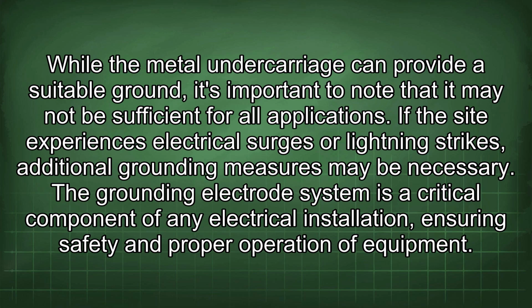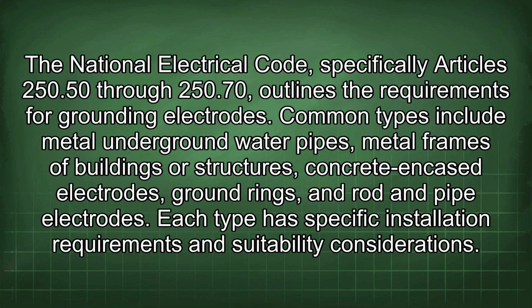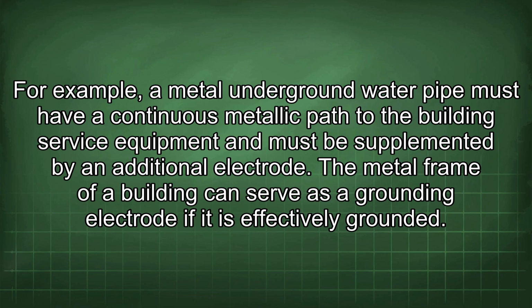The grounding electrode system is a critical component of any electrical installation, ensuring safety and proper operation of equipment. The National Electrical Code, specifically Articles 250.50 through 250.70, outlines the requirements for grounding electrodes. Common types include metal underground water pipes, metal frames of buildings or structures, concrete encased electrodes, ground rings, and rod and pipe electrodes. Each type has specific installation requirements and suitability considerations. For example, a metal underground water pipe must have a continuous metallic path to the building service equipment and must be supplemented by an additional electrode.